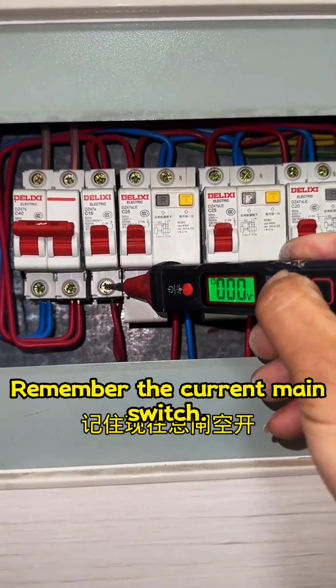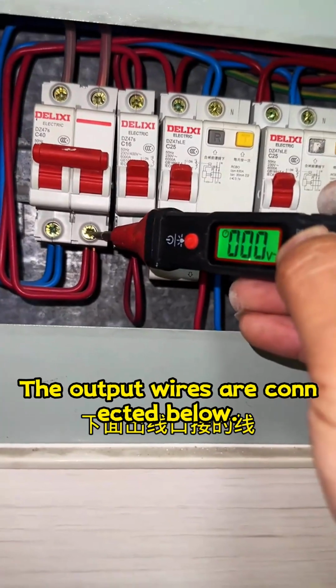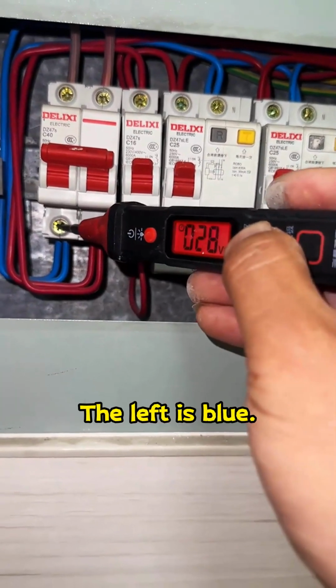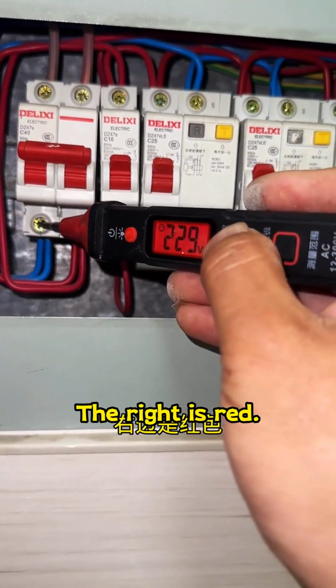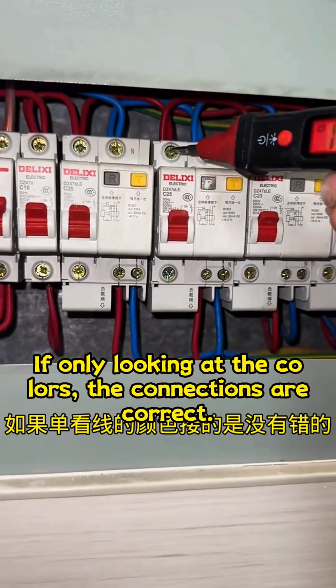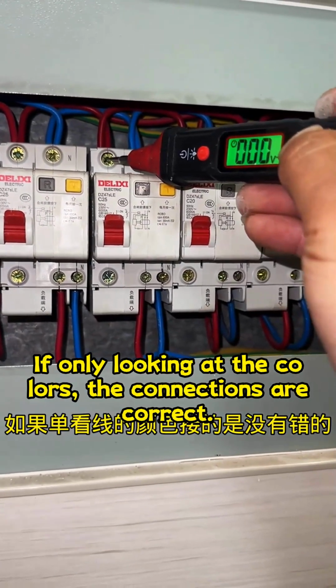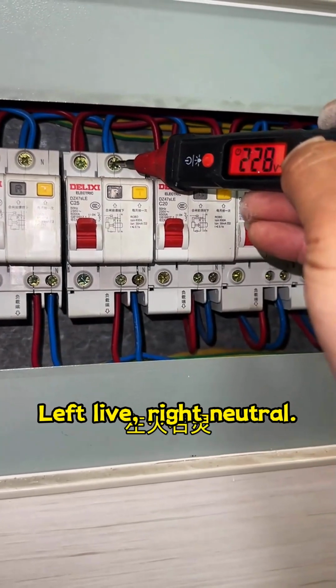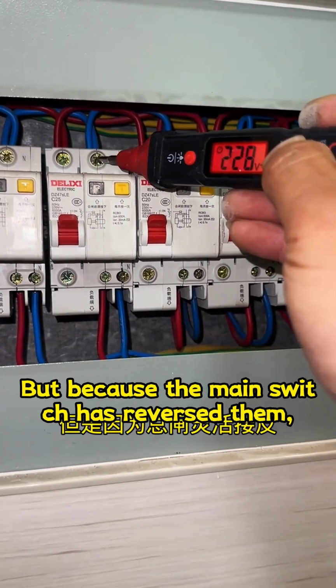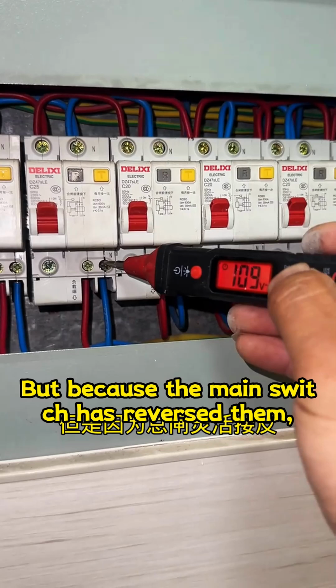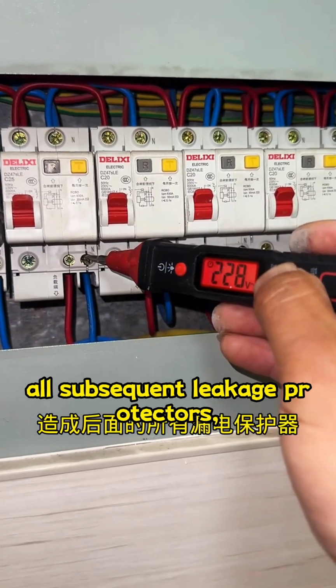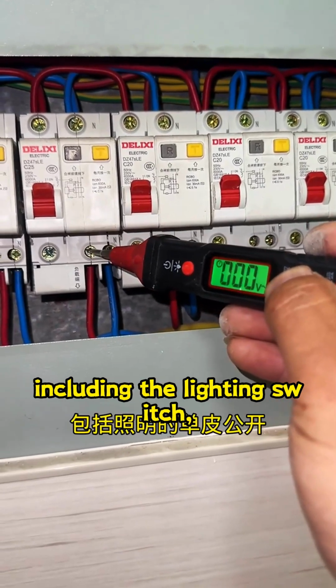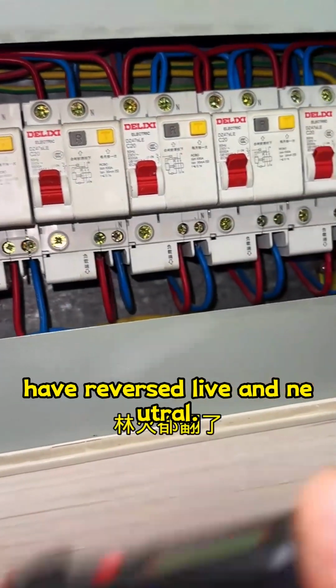Remember the current main switch. The output wires are connected below. The left is blue. The right is red. If only looking at the colors, the connections are correct. Left neutral, right live. But because the main switch has reversed them, all subsequent leakage protectors, including the lighting switch, have reversed live and neutral.